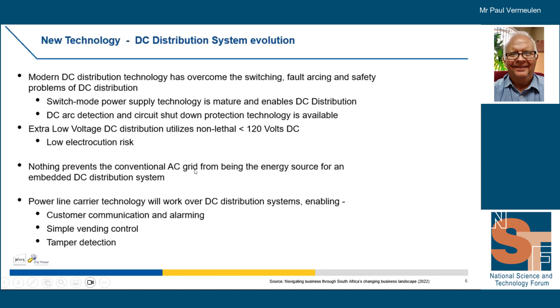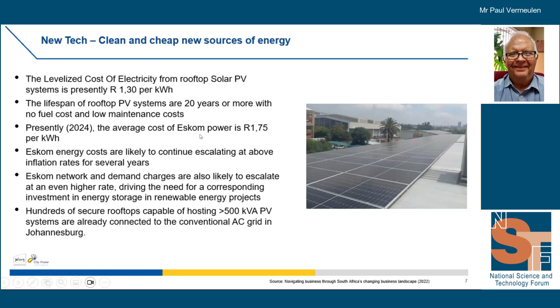Levelized cost of rooftop is about R1.30 per kilowatt hour, and it should last for 20 years. The average cost of Eskom power has now just gone up. It's close to R1.75 per kilowatt hour, and those costs are likely to carry on escalating as time goes by. And what you're also going to find is that the network and demand charges that Eskom charge are also likely to escalate at an even higher rate, because they've got to now accommodate the new peakiness of the demand, if you like. And that will drive the need on our side for a corresponding investment in energy storage in any renewable energy project. We've got to really start thinking seriously about co-investment with storage and renewables. And in Joburg, certainly we've got hundreds of secure rooftops that are quite capable of hosting 0.5 megawatt PV systems, and they're already connected to the grid.